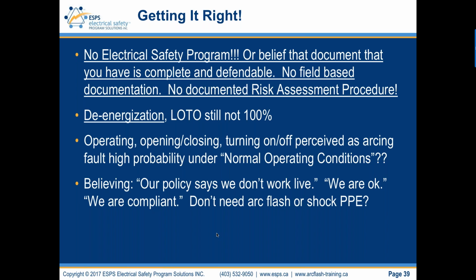Again, operating, opening, closing, turning on and off, perceived as an arcing fault, high probability under normal operating conditions. We need to change that perception. That is not a true statement. Right, so we need to manage that one. We need to get more communication out there and get everybody on the same page. Companies believe that their policy says they don't work live, that they're okay, and that they're compliant, and that they don't need arc flash and shock PPE because they're turning the power off.